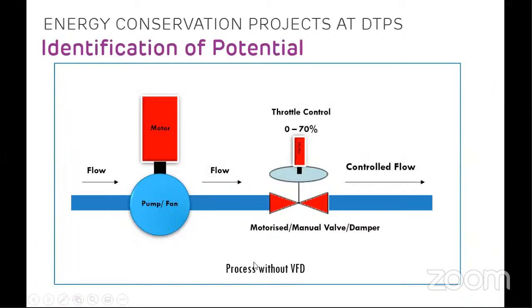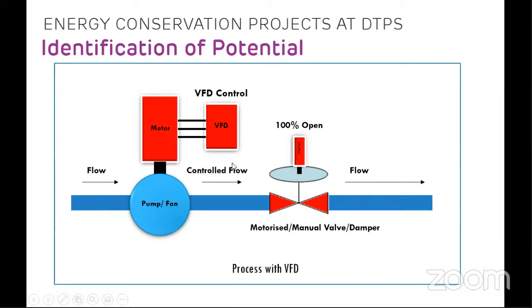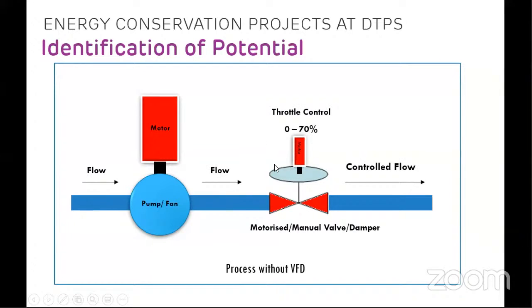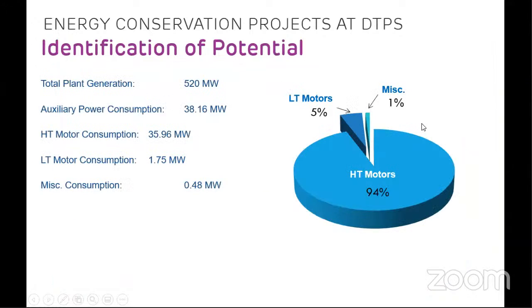So here we have seen that a process without VFD has losses across a motorized valve or a damper. When the process is installed with VFD, by reducing the speed of the motor, we can eliminate these losses and save energy. So VFDs give tremendous potential wherever there is a throttled valve or a damper. Only in those applications can we install VFDs. However, if the pump or fan is always running at full flow and the process requires that full flow, then there is no point in installing a VFD. There will not be any saving.